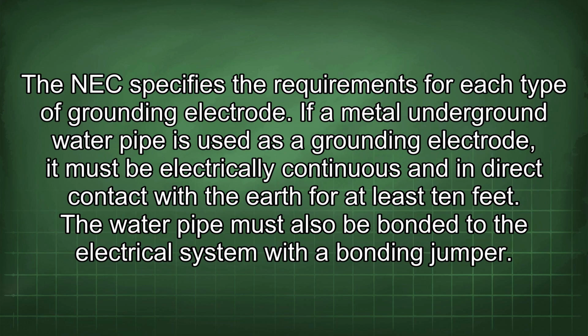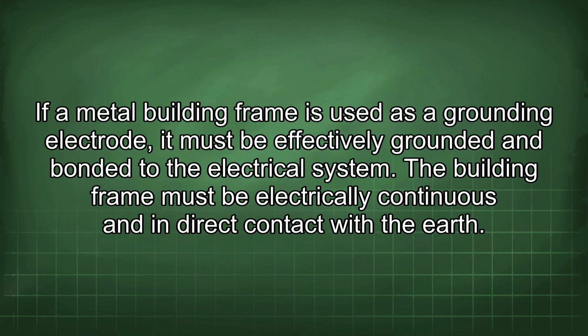The NEC specifies the requirements for each type of grounding electrode. If a metal underground water pipe is used as a grounding electrode, it must be electrically continuous and in direct contact with the earth for at least 10 feet. The water pipe must also be bonded to the electrical system with a bonding jumper. If a metal building frame is used as a grounding electrode, it must be effectively grounded and bonded to the electrical system. The building frame must be electrically continuous and in direct contact with the earth.